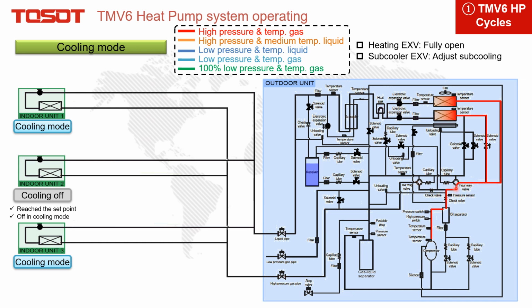and then this one will go. It is cooling mode, so we just turn right and go to the outdoor heat exchanger to release heat. Then it becomes fully liquid. Then it gets through these fully open heating EXVs, these two. Then the target is the indoor unit. And also, since it is cooling mode, a bypass from here will get through this EXV, and this part of the refrigerant will become cooler, then absorb heat from this main row, then itself will become gas and go to the gas liquid separator. Then the main row, which is this part, becomes cooler to increase the subcooling.